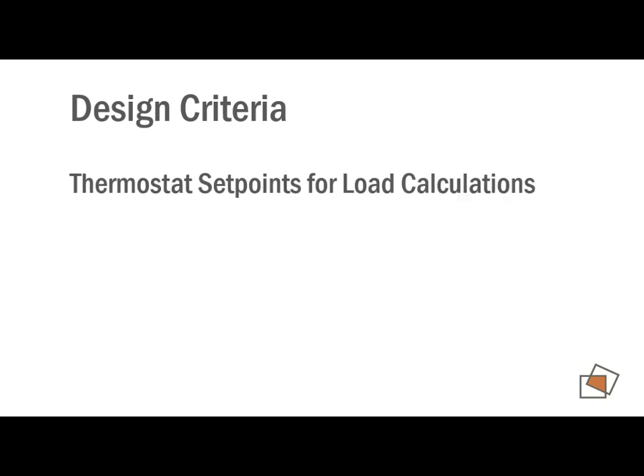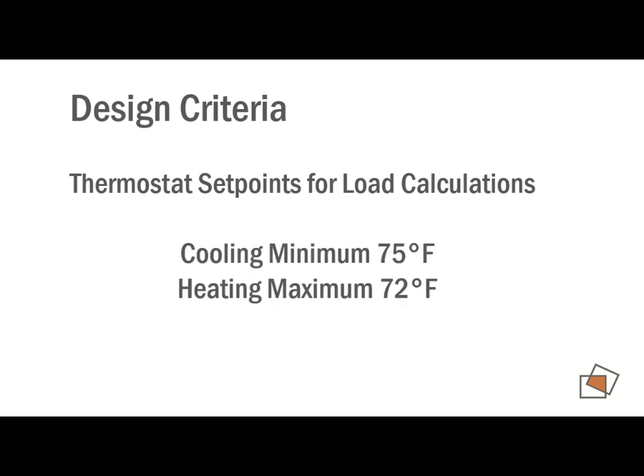zone you're in. Another thing it dictates to us is thermostat set points that we have to use in our load calculations. So the code says that your minimum thermostat set point is 75 degrees and your maximum 72 degrees. That doesn't mean you can't set your thermostat to 72 in your building, but it's saying when we're doing our load calculations, this is what it expects us to design to, which is kind of interesting. Maybe a conversation that may change some design practices.